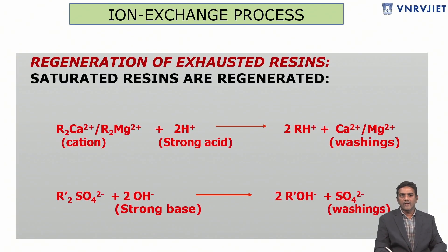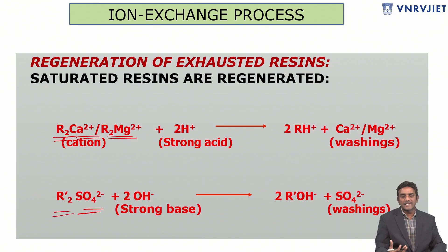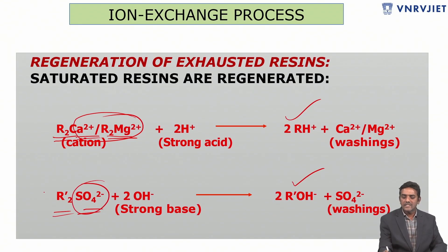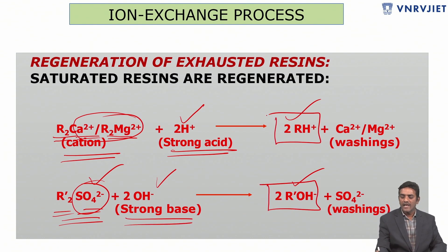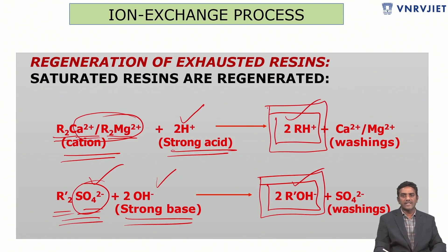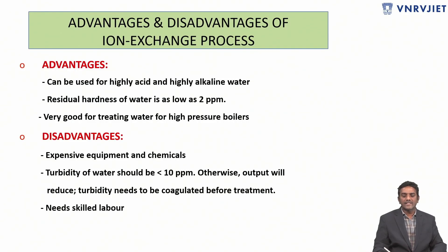H⁺ ions released from the cation exchanger and OH⁻ ions released from the anion exchanger together with our water produce pure water — H₂O — that is deionized water. Moving on to regeneration: we must regenerate the resins because they are bound with calcium, magnesium, and sulfate ions. Since resins are costly, we must wash acidic resins with strong acid and basic resins with strong base to restore them as R-H⁺ and R-OH⁻, ready to be reused.